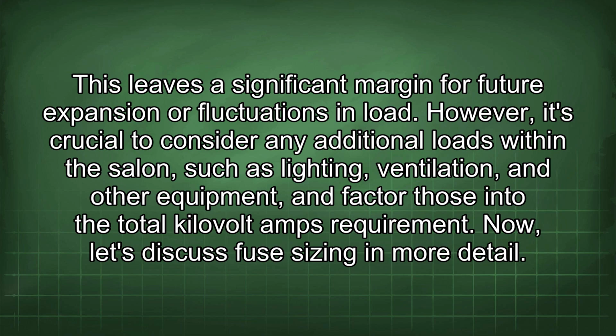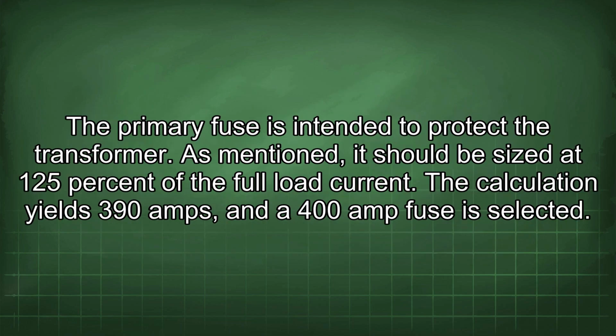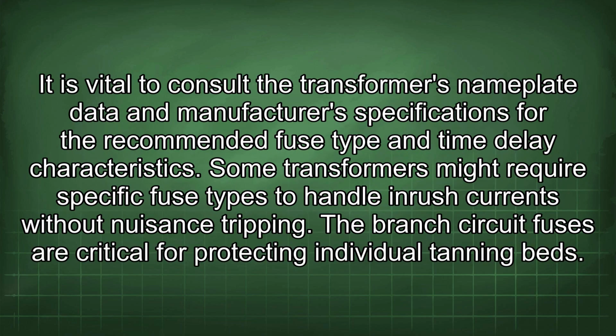Now, let's discuss fuse sizing in more detail. The primary fuse is intended to protect the transformer. As mentioned, it should be sized at 125% of the full load current. The calculation yields 390 amps, and a 400 amp fuse is selected. It is vital to consult the transformer's nameplate data and manufacturer's specifications for the recommended fuse type and time delay characteristics. Some transformers might require specific fuse types to handle inrush currents without nuisance tripping.